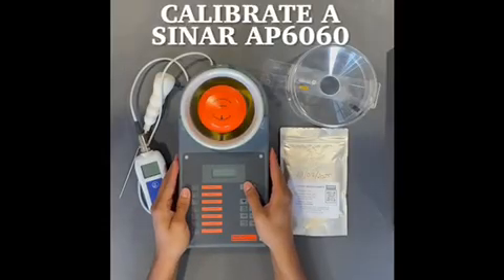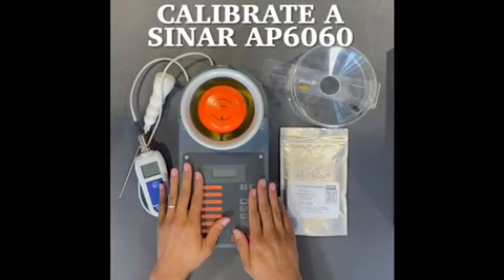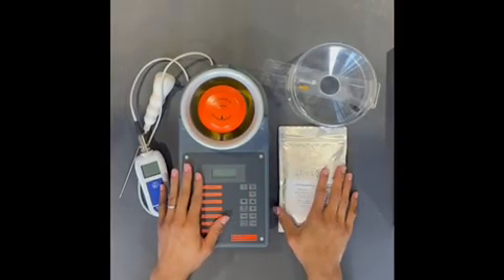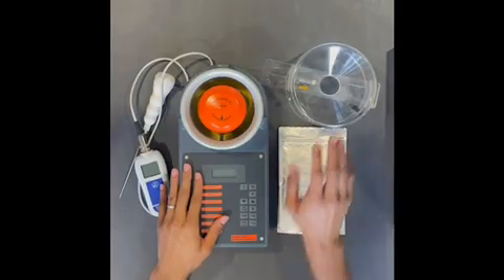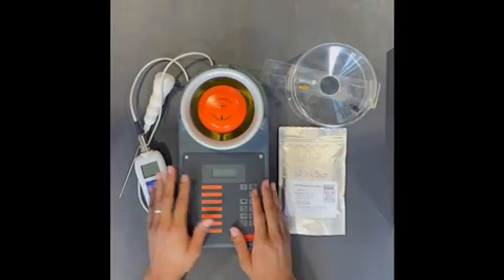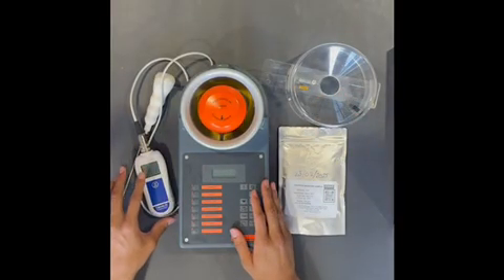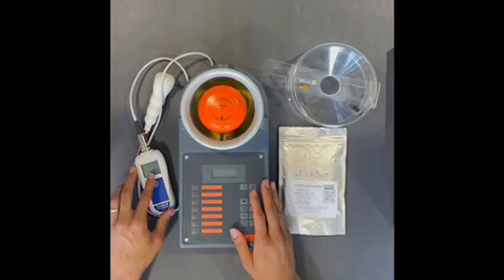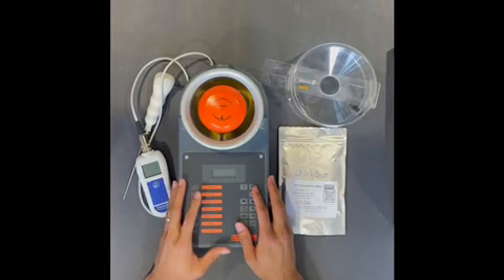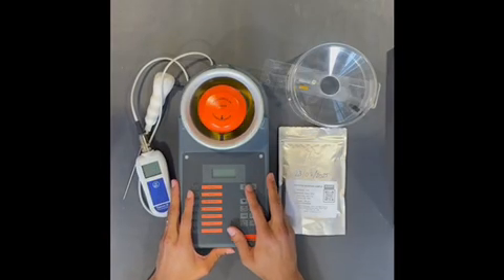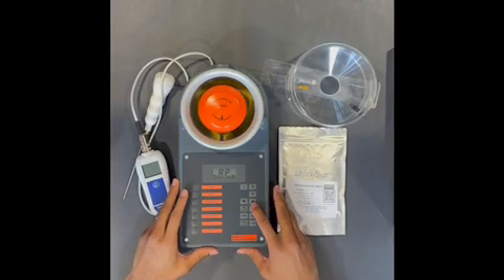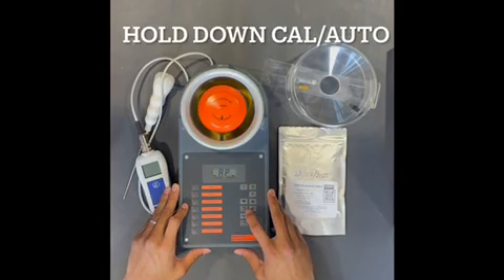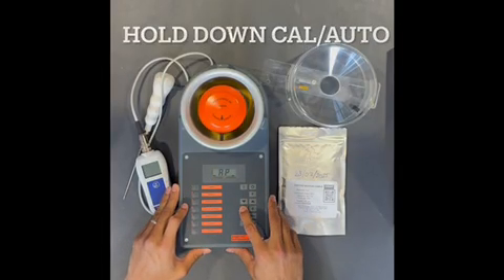So we want to first receive our machine, make sure we've got a calibration sample with the machine. We want to make sure we have our hopper, and if we do have a temperature probe, that's best. If not, we'll have to go with using room temperature. We want to turn on the machine, and we want to hold down Cal Auto for 3 seconds.